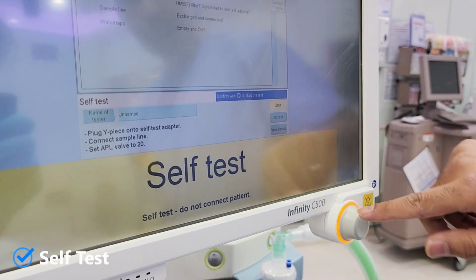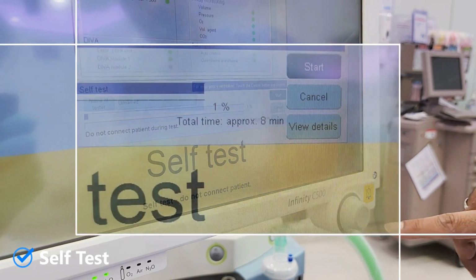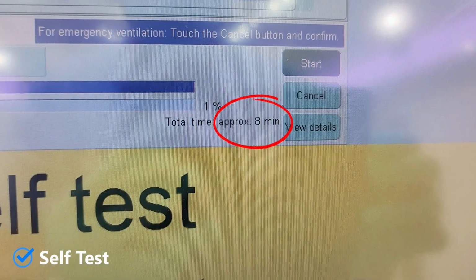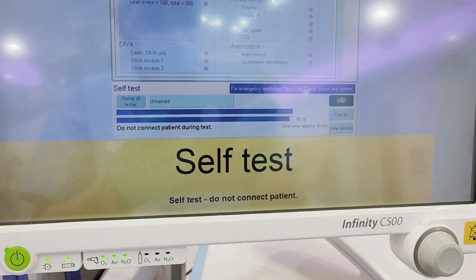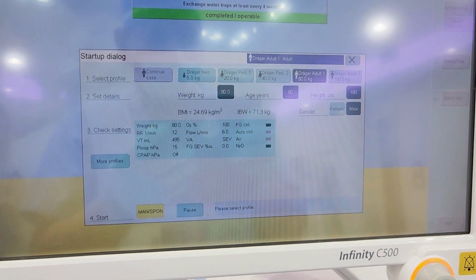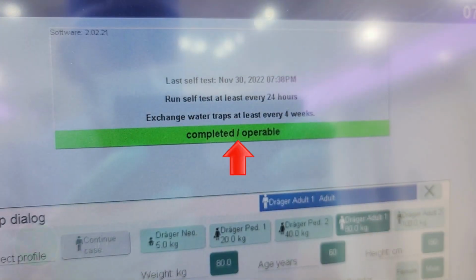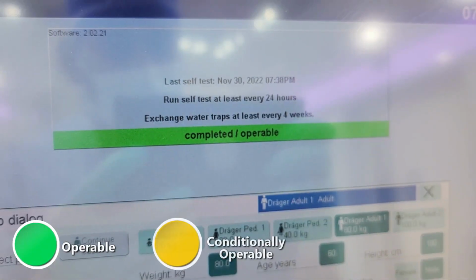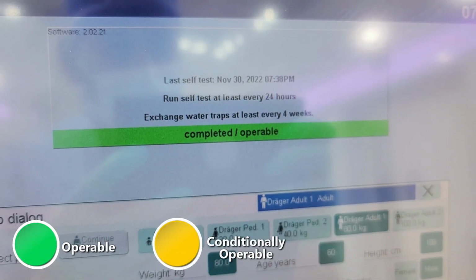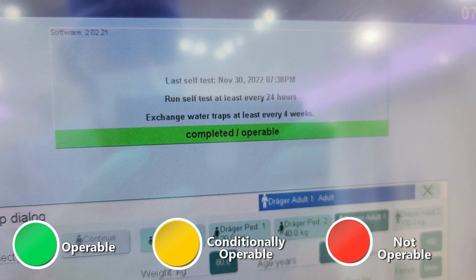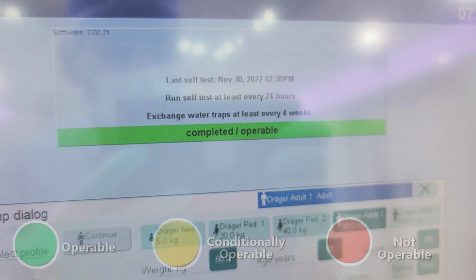Once you have completed the manual checklist, confirm the self-test start button. The self-test will take around 8 minutes. After the self-test is completed, the machine automatically goes to standby mode. The green color here indicates that the machine is fully operable. If it is yellow, the machine is conditionally operable. And if it is red, don't use it. The machine should be sent to biomedical.